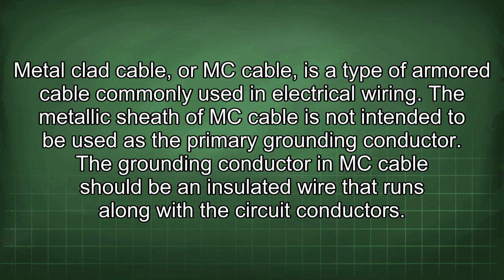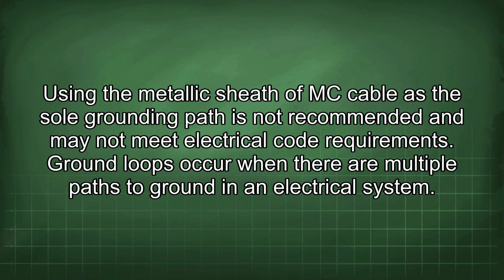Metal-clad cable, or MC cable, is a type of armored cable commonly used in electrical wiring. The metallic sheath of MC cable is not intended to be used as the primary grounding conductor. The grounding conductor in MC cable should be an insulated wire that runs along with the circuit conductors. Using the metallic sheath of MC cable as the sole grounding path is not recommended and may not meet electrical code requirements. Ground loops occur when there are multiple paths to ground in an electrical system.